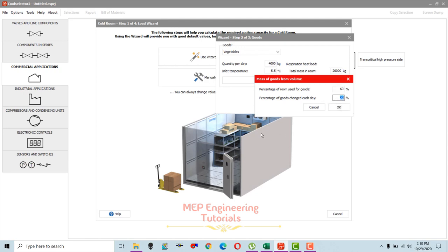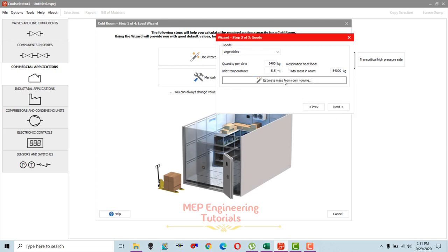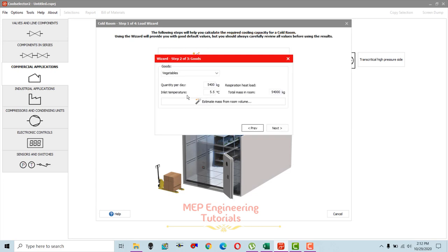For percentage of goods changed each day, you will put new food in and replace the used food. We're going to set this to 10 percent — meaning 10 percent of goods are replaced each day. Select OK. The estimated total mass in the room is 54,000 kg, and quantity per day is 5,400 kg, meaning we replace this quantity every day.